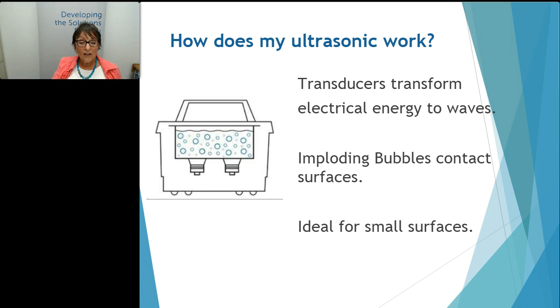So how does my ultrasonic work? There's little transducers inside the chamber, as you can see, hidden. You don't typically see this. The transducers are transforming electrical energy to waves and then creating these little bubbles that actually implode. They're not exploding, they're imploding on the surface, and that actually pushes soils off. And this is ideal for small surfaces like dental instruments. So it's really an ideal cleaning device for a dental office.